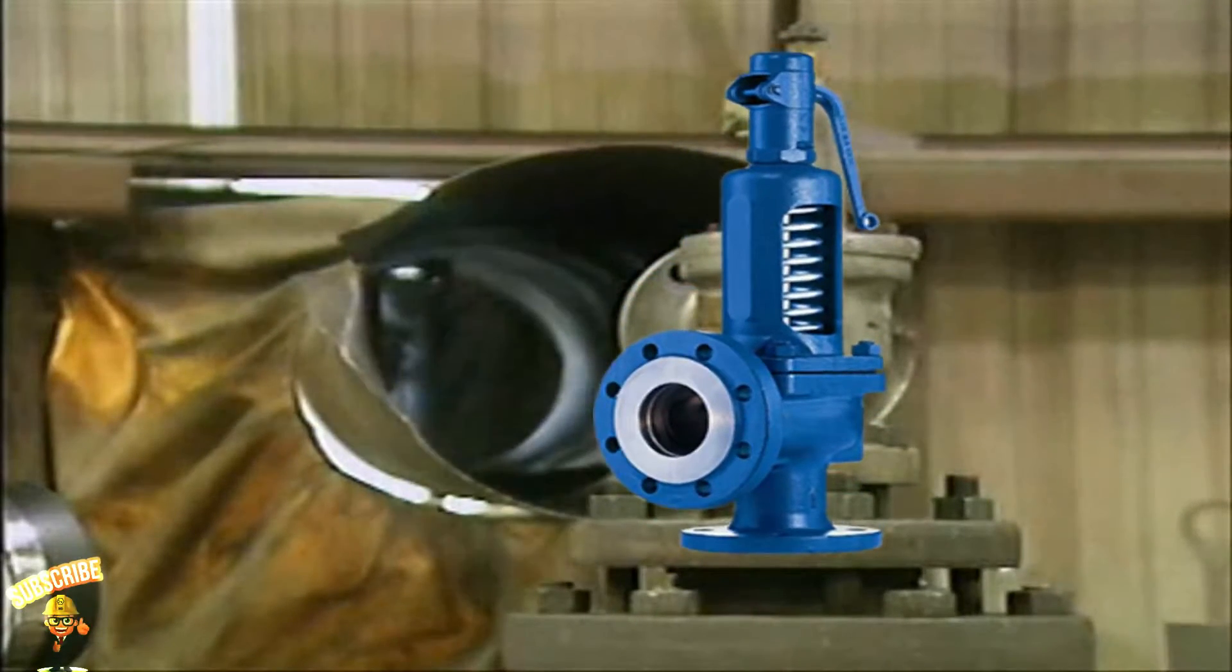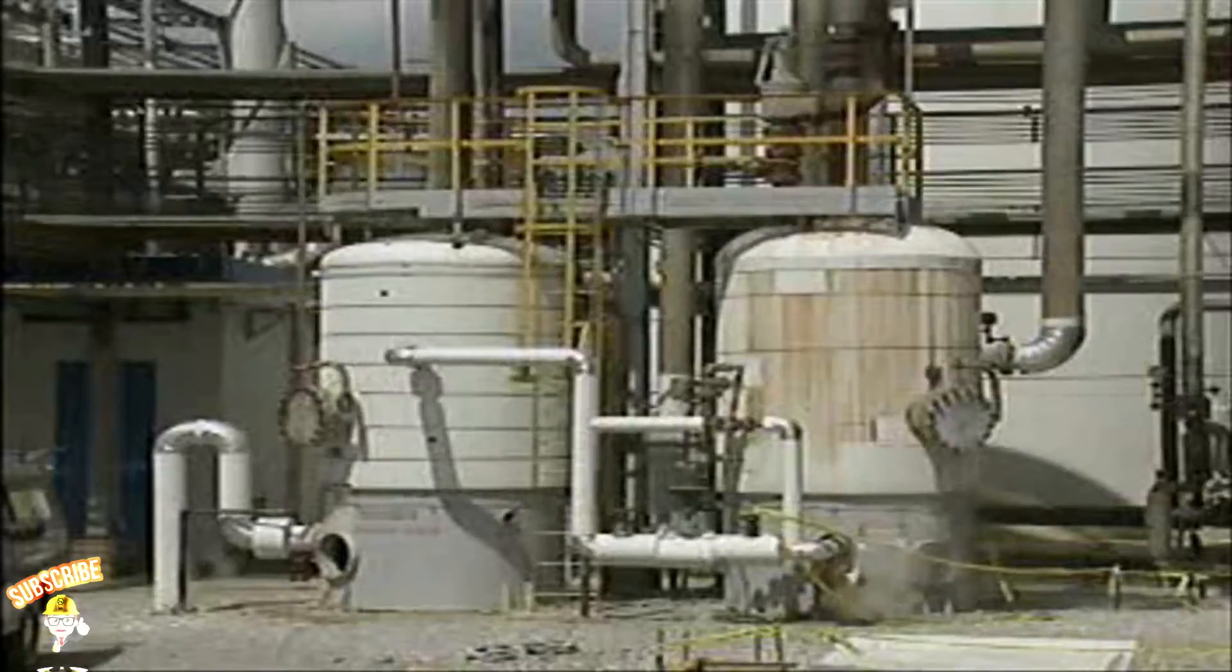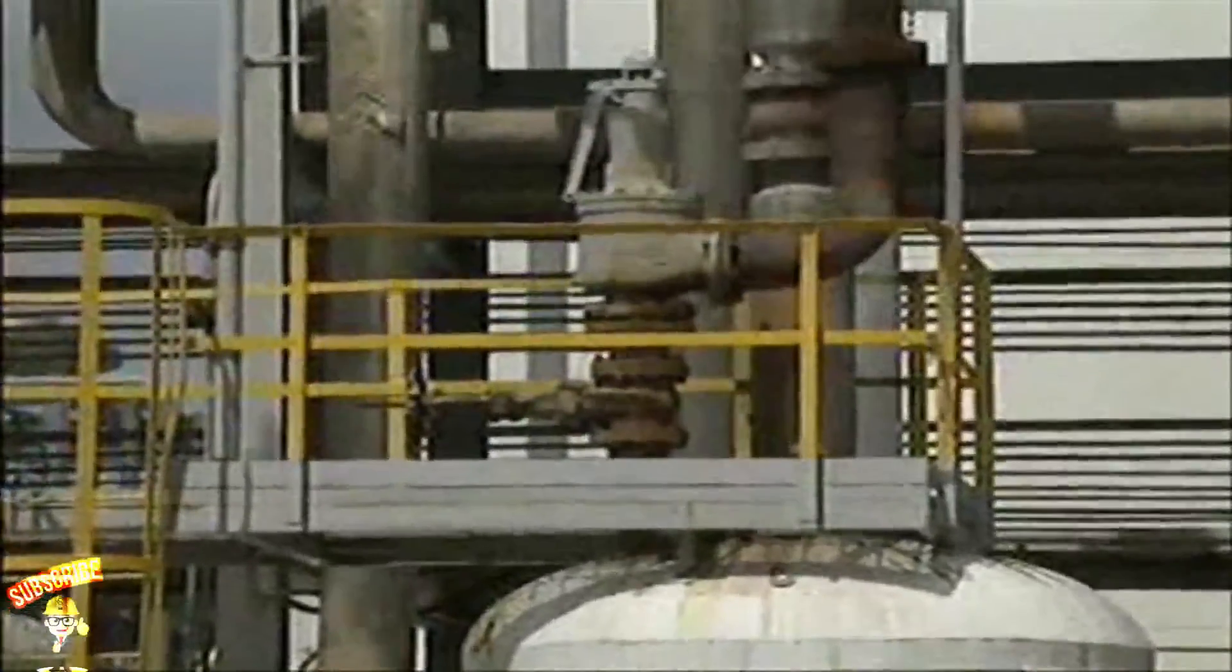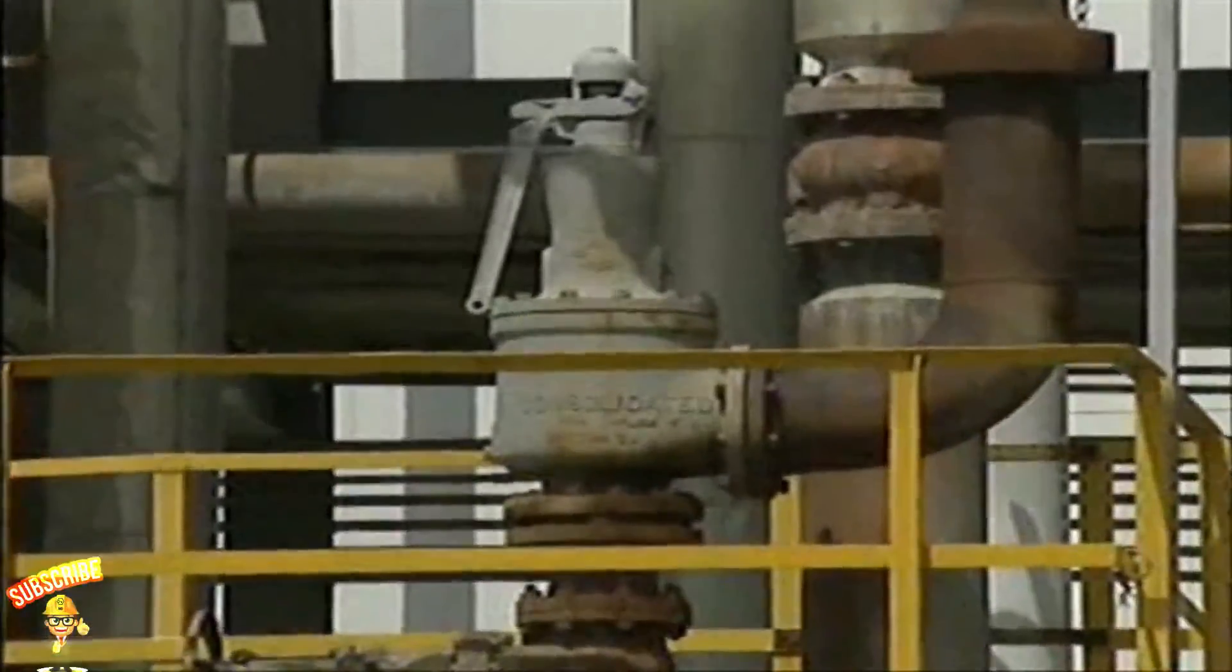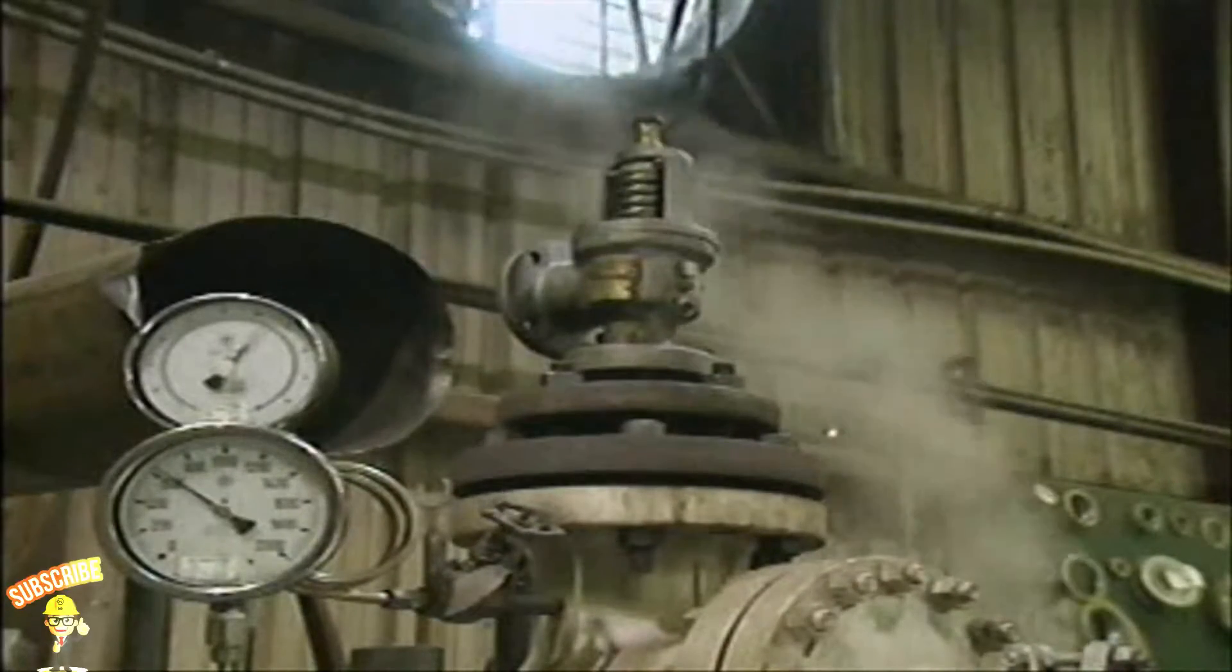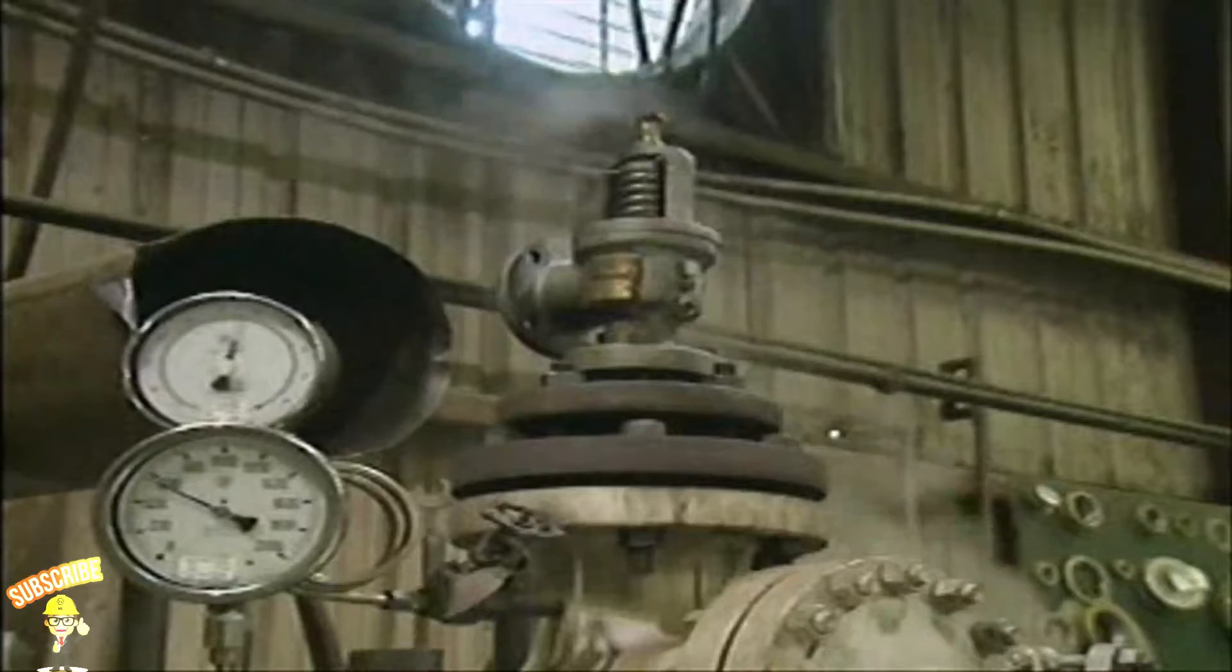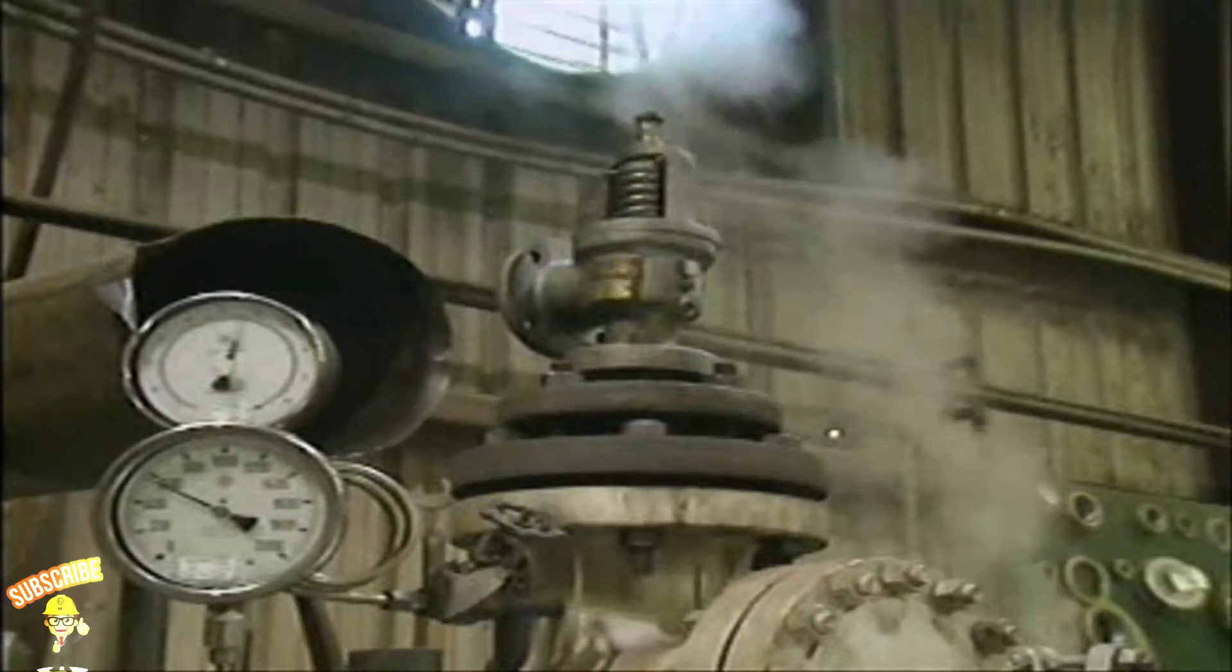Safety valves are able to quickly let out large volumes of gas or steam to relieve excess pressure. They're commonly used on gas or steam lines because the volume of gas or steam increases as pressure decreases, and gas under pressure may expand to a tremendous volume when pressure is relieved. Safety valves open wide very quickly and stay open until system pressure drops a predetermined amount below the point at which the valve is set to open, allowing large volumes of gas to escape.